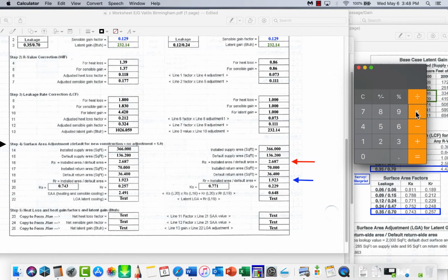All right, now we got the corrected factor. Same thing, 4 times 0.648. There you go. It's not even 6,000, not even half a ton. So, I mean, that's what I'm saying. By doing stuff like sealing ductwork and putting insulation on there, this really shows how much you can actually reduce your loss and your heat gains in your home just by fixing this. I've always said that the ductwork is our main problem. Our units are fine. It's just the houses and the ductwork where we need to work on.